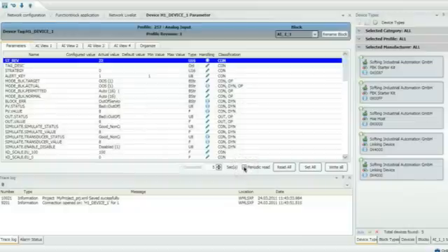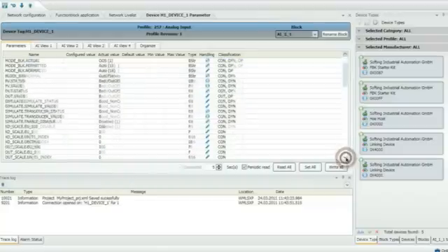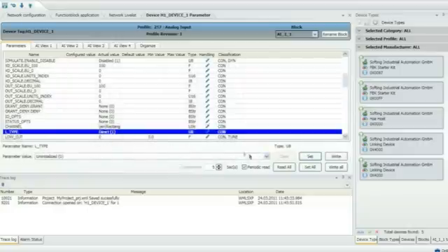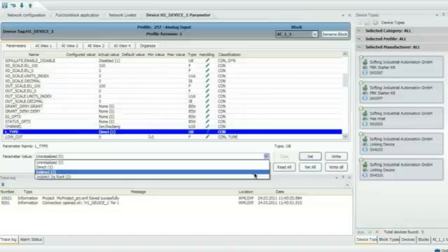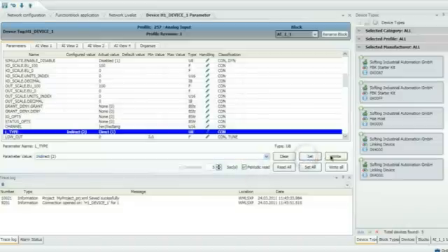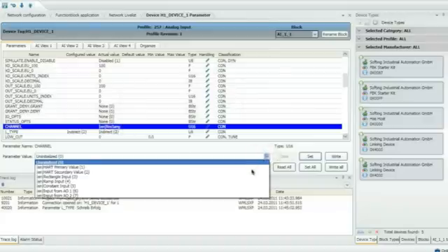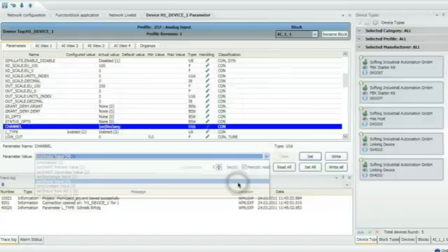If you like to see the current process value, you have to make sure that the AI function block is in auto mode. To transition the function block into auto mode, we have to change the settings of a few function block parameters. The following steps apply to our sample application only. Please note that for some applications, devices, these parameters have already the correct value.